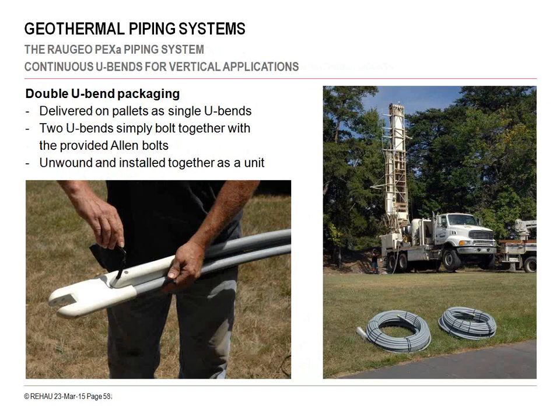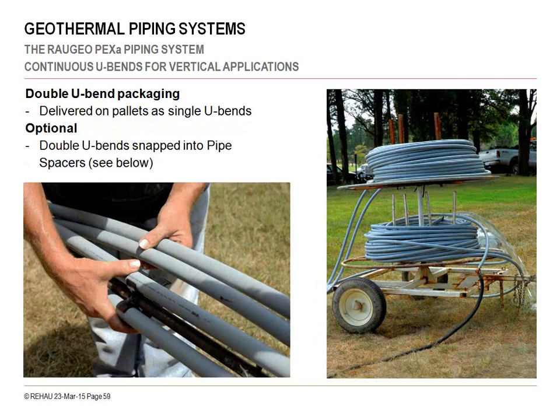Here you can see the 2 U-bends being nested and the installer fastening those probe tips together. They come out to the project site on a pallet as 2 single U-bends with the white probe tips at the ends. We're a big advocate for utilizing pipe spacers along the length of the pipe. What that does is keep the U-bends up close to the perimeter of the borehole where you want it for heat exchange. And it also equally spaces your 2 supply and 2 return pipes to minimize thermal interference. The image on the right is showing the 2 individual coils. It's hard to see, but at the bottom left, that's the nested 2 white probe tips, just getting ready to be inserted down a vertical borehole.